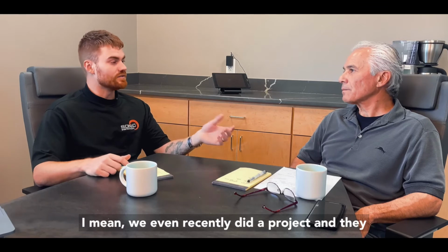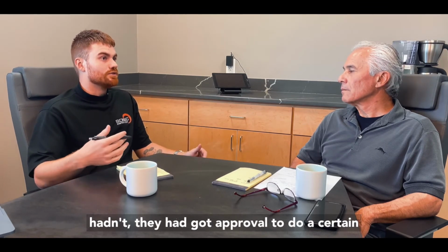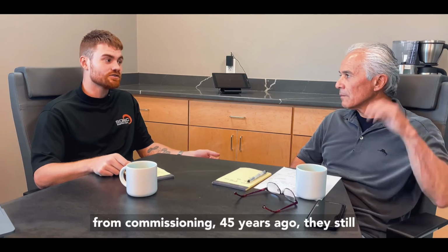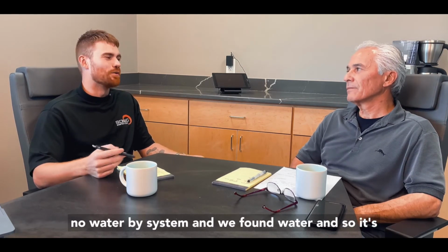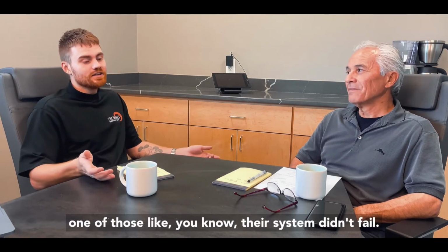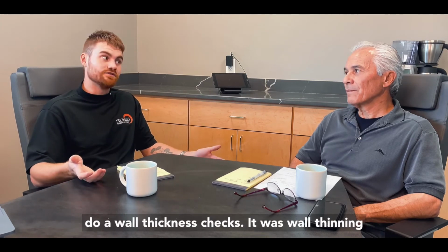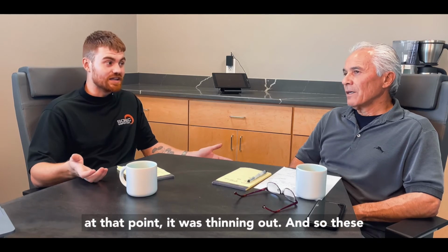Sure. We even recently did a project, and they had got approval to do a certain type of partial trip test, and from commissioning 45 years ago, they still had water in their system. The guy said, "There's no water in my system," and we found water. Wow. Their system didn't fail, but in the areas where we found water and started doing wall thickness checks, it was wall thinning at that point. It was thinning out.